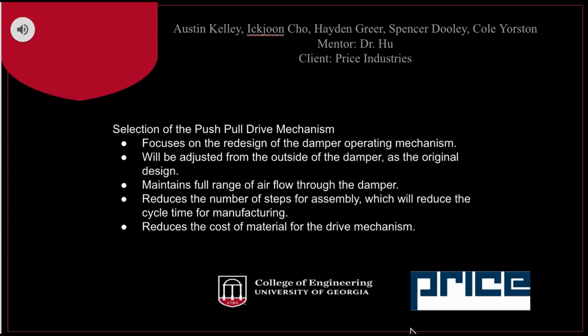After considering both design options, we decided to choose the push-pull mechanism. There are a few reasons why we chose this option. This design focuses on the redesign of the damper operating drive mechanism, since it is the most costly part of the current design. It will be adjusted from the outside of the damper in the same manner as the original design. It maintains full range of airflow through the damper. This design will reduce the number of steps for assembly, which will reduce the cycle time. It will also reduce the cost of material for the drive mechanism.